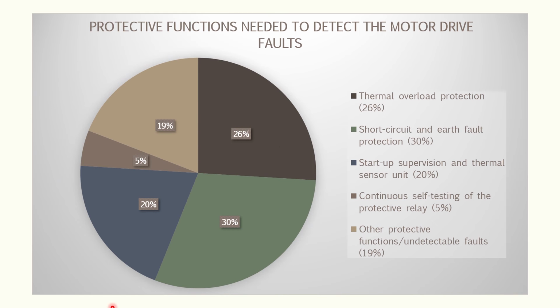This is the pie chart for the protective functions needed to detect the motor drive faults. So 30% we have short circuit and earth fault protection, followed by thermal overload protection with 26%, start-up supervision and thermal sensor unit with 20%, 19% for other protective functions/undetectable faults, and 5% for continuous self-testing of the protective relay. So these are the protective functions we need when we are dealing with motors.